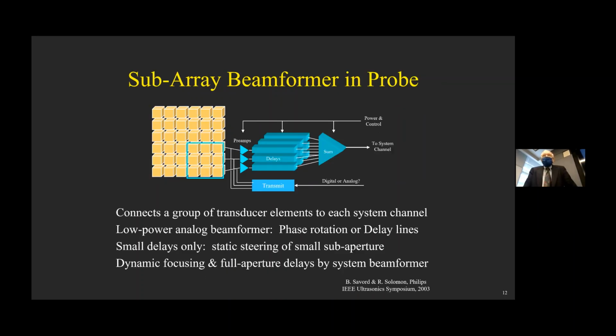Okay. Now, the other approach is to use what's called a sub-aperture beamformer. The people who talked about this in the literature first actually were from Philips. And the idea was that you take a subset of the full aperture and connect those elements densely to a sub-aperture beamformer, I'm going to call it here. So there are typically analog, very low power analog ways of doing that beamforming and doing phase rotations or delay lines, passive delay lines, whatever sorts of things. And those are, if you will, the small delays or the fine timing changes. And then the big timing changes you leave to be done back at the system end, usually in the console, but not necessarily.